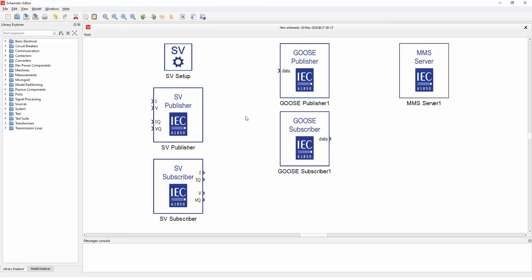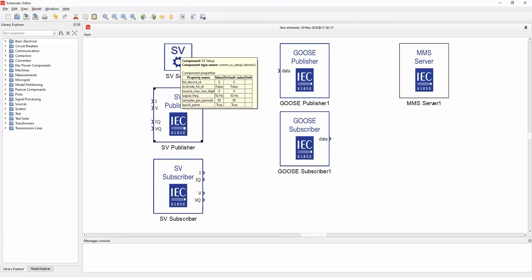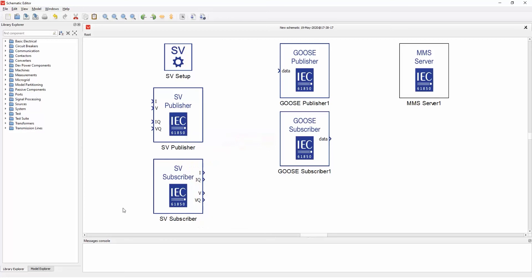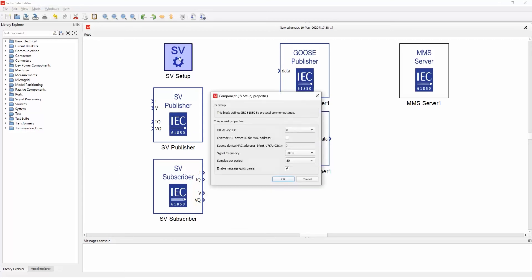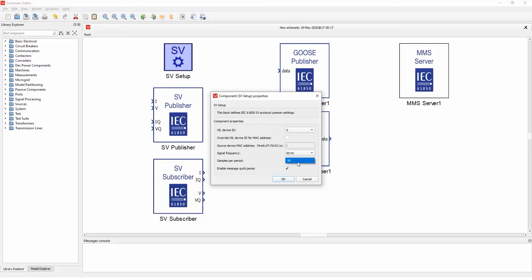So let's start with the SV protocol. We have the SV setup, SV publisher, and SV subscriber. Inside the SVE setup, we can set the signal frequency and samples per period for each of the HIL devices that you can choose here. For 50 and 60 Hz we have 80 samples per period, and for the lower frequency we can go to 256 samples.